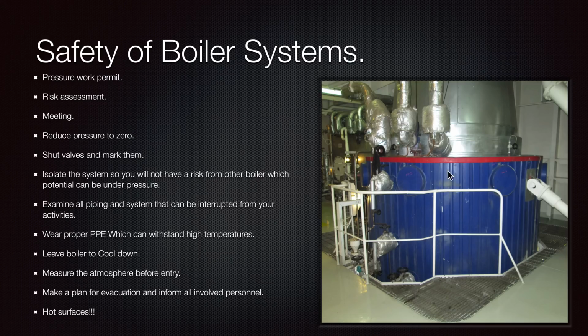So when you depressurize one boiler and you have the other one pressurized, be sure that you have isolated the other boiler too, so you will not get any pressure running from one boiler to another as an emergency situation that can happen unpredictably.